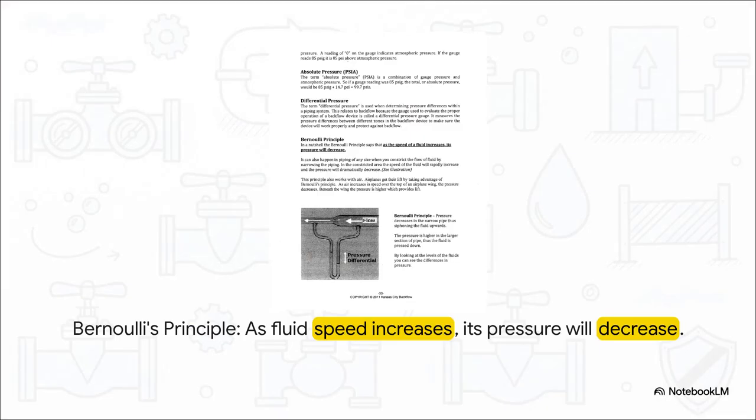And this slide right here shows you exactly why that pressure difference is so critical. There's a concept called Bernoulli's principle. It sounds complicated, but it's not. It just says that when water moves faster, its pressure drops. This is what causes backsiphonage. Imagine a firefighter opens a hydrant down the street. Water starts rushing through the main. Its pressure plummets, and suddenly you've got a vacuum in the system ready to suck stuff in.